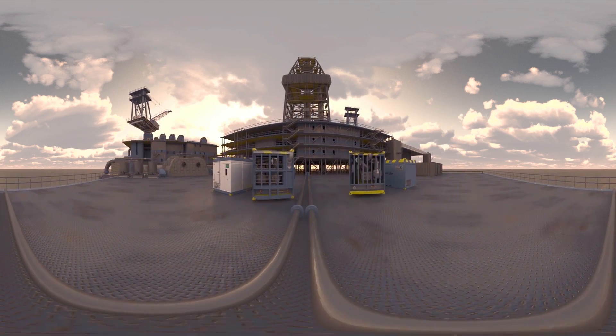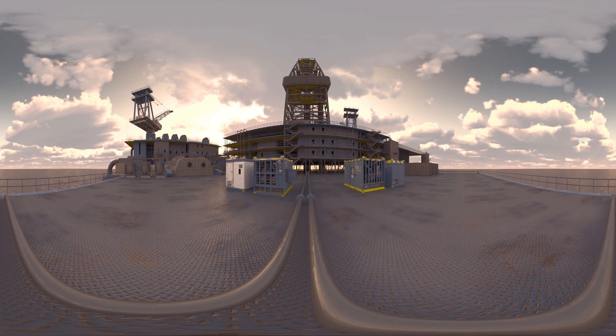In our scenario, a rig-safe compressor located 3 metres from a temporary line containing hydrocarbons is compliant with current regulations. Air is constantly circulated through the enclosures to cool hot surfaces. On detection of gas, the Zone 2 compressor employs systems to prevent ignition and shuts down automatically, forming a gas-tight seal, thus allowing safe manual ESD activation, common in well-testing situations. In the scenario described, the rig-safe compressor with multiple sources of ignition will continue to operate, but with potentially catastrophic consequences.